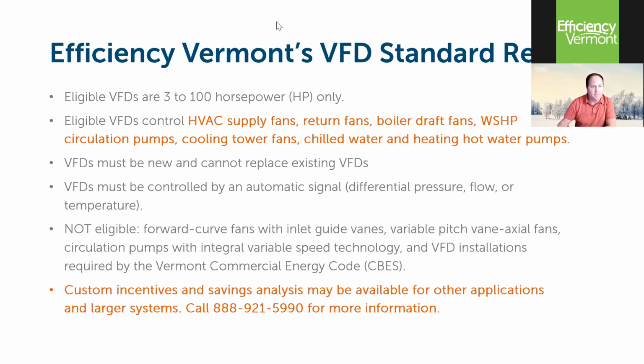This third bullet, VFDs must be new and cannot replace existing VFDs. I really kind of should put a ring fence around this, because I said before, I still would like folks to bring these to us. If there is a case to be made that, yes, I can run this across the line, there's no code requirement or otherwise requirement that says I have to replace the VFD, then I think we have a good case to extend an incentive and help you get into a replacement VFD.